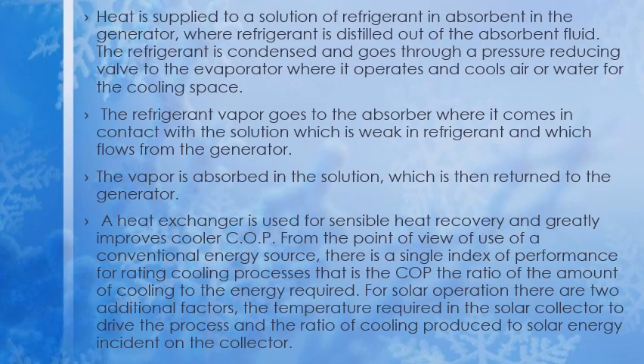Heat is supplied to a solution of refrigerant in absorbent in the generator, where refrigerant is distilled out of the absorbent fluid. The refrigerant is then condensed and goes through a pressure reducing valve to the evaporator, where it evaporates and cools air or water for the cooling space. The refrigerant vapor goes to the absorber, where it comes in contact with the solution, which is weak in refrigerant and flows from the generator. The vapor is then absorbed in the solution, which is then returned to the generator.